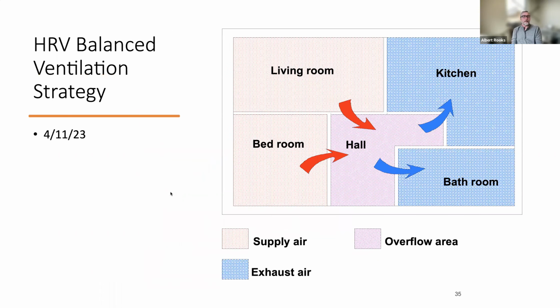The way we try to treat that with ventilation is we create cascading ventilation. We try to create a system that covers all rooms. So we go from positive pressure, the red arrows, to negative pressure, the blue arrows. In any floor plan, we would generally put the supply flow of the ventilation system primarily into the bedroom and the living room. We create a pathway where it flows into those areas at a very slow rate, where we don't hear it or feel it, because we don't need a lot of airflow, since we're not trying to heat or cool the building with it, which takes a lot of airflow. So we provide fresh air into the living room and bedroom, set it up so it can flow over hallways, and then create negative pressure points in the kitchens and bathrooms.